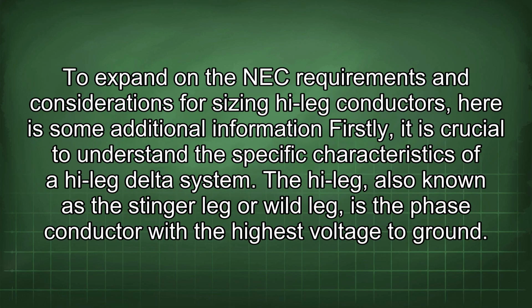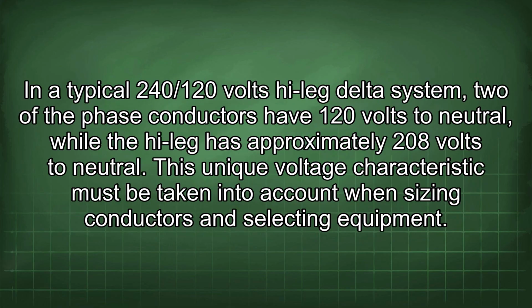To expand on the NEC requirements and considerations for sizing high leg conductors, here is some additional information. Firstly, it is crucial to understand the specific characteristics of a high leg delta system. The high leg, also known as the stinger leg or wild leg, is the phase conductor with the highest voltage to ground. In a typical 240/120 volts high leg delta system, two of the phase conductors have 120 volts to neutral, while the high leg has approximately 208 volts to neutral. This unique voltage characteristic must be taken into account when sizing conductors and selecting equipment.